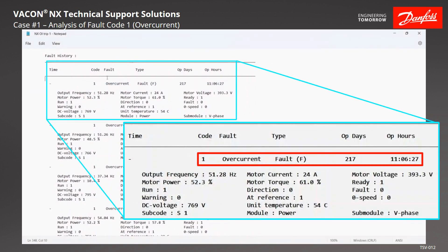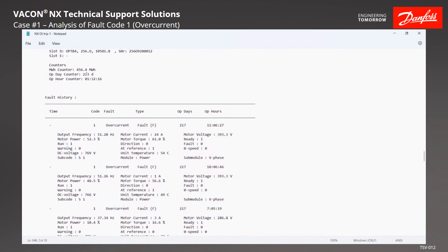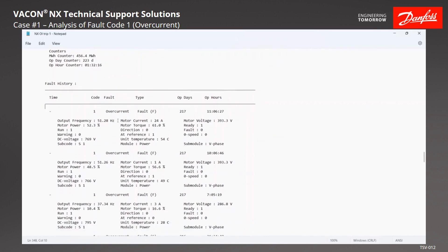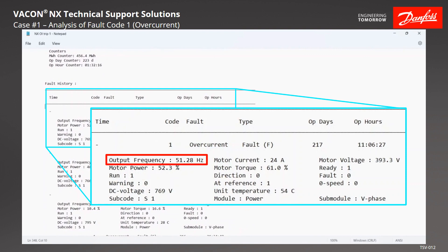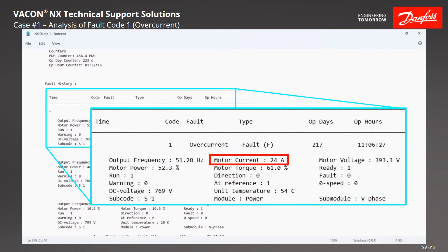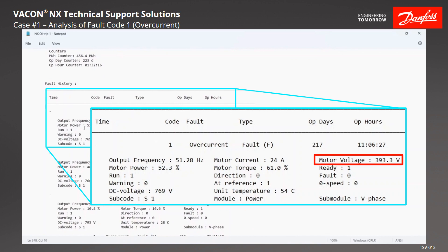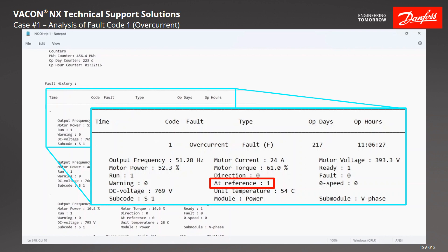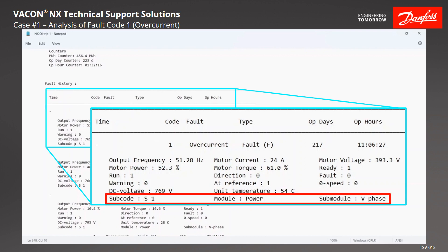You can see it's fault code 1, an overcurrent, which happened at 217 days, 11 hours, 6 minutes, 27 seconds. Compared to when this was printed at 223 days, 1 hour, 32 minutes and 16 seconds — so roughly 6 days ago. The output frequency was at 51.28 Hz. Motor current was 24 amps. Motor voltage at 393.3 volts. Motor power 52.3%, motor torque at 61%. We were ready, running, direction was forward, not in fault or warning, at reference, not at zero speed. DC bus was 769 volts, unit temperature 54°C. Subcode S1, power module, V phase.